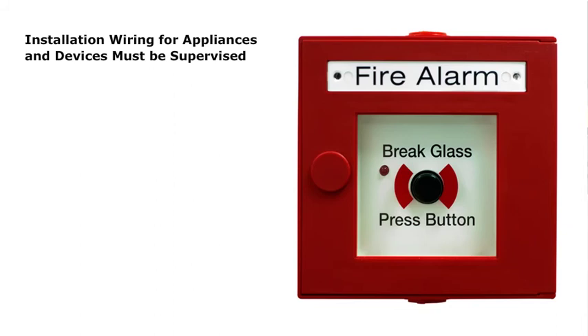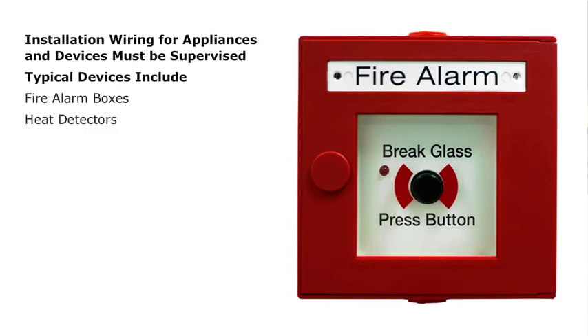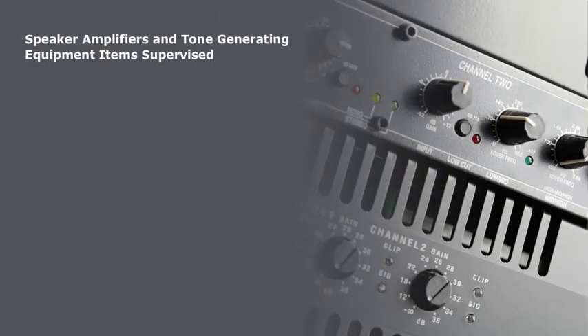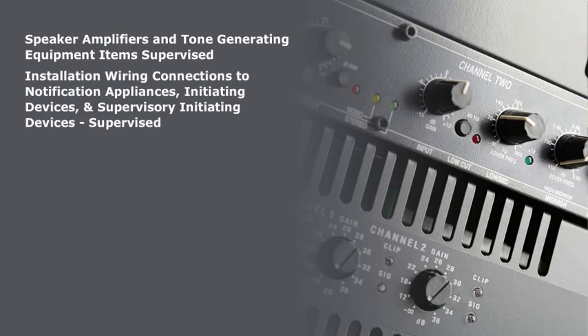Installation wiring for appliances and devices that initiate and transmit signals must be supervised. This applies to devices that are manual and automatic. Typical devices include fire alarm boxes, heat detectors, smoke detectors, and automatically operated transmitters. All installation wiring for operating audible and visual alarm notification circuits are electrically supervised. Speaker amplifiers and tone-generating equipment items are supervised. Installation wiring connections to alarm notification appliances, initiating devices, and supervisory initiating devices are supervised.